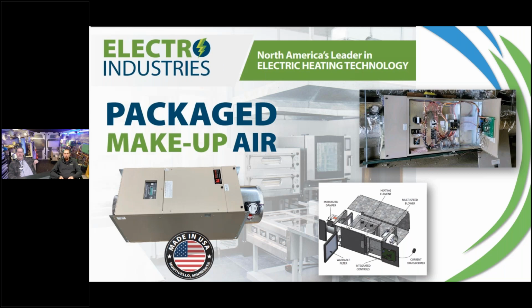This is code compliant because of the built-in heater below 50 degrees—that's when we use that element. We also have a filter that's really just for particulates coming in from outside, bugs and so forth, protecting the inner workings of this makeup air unit.